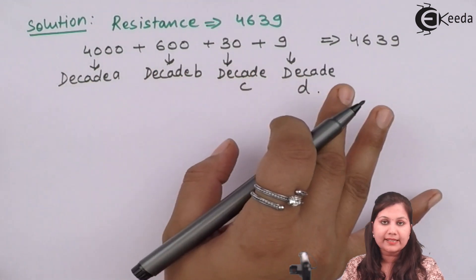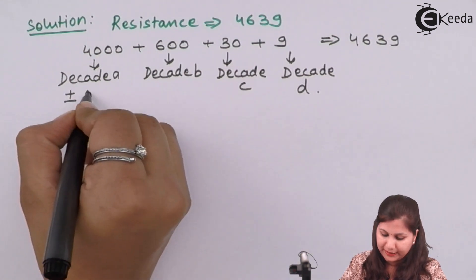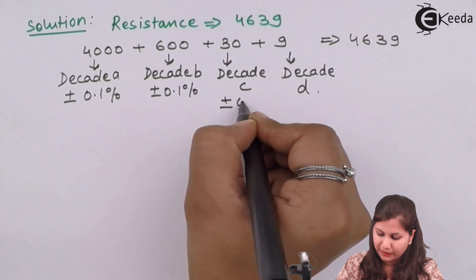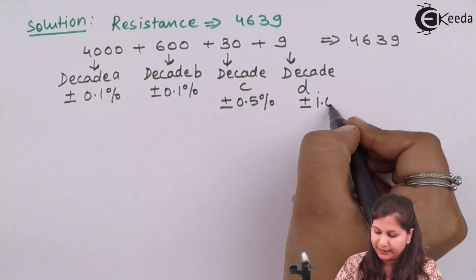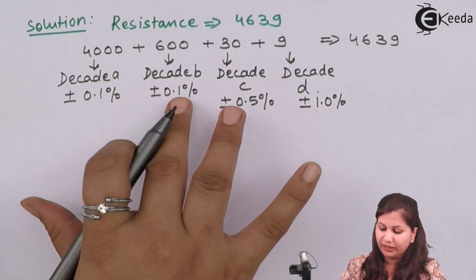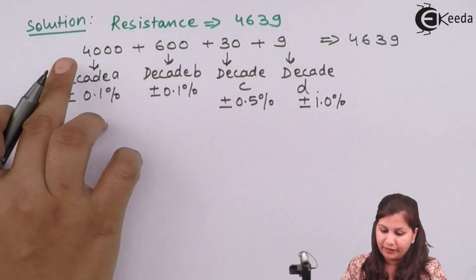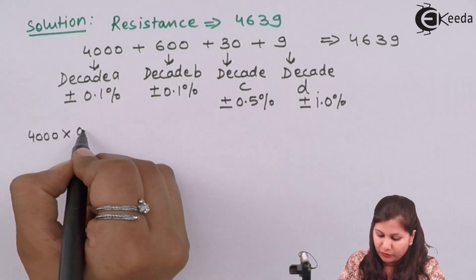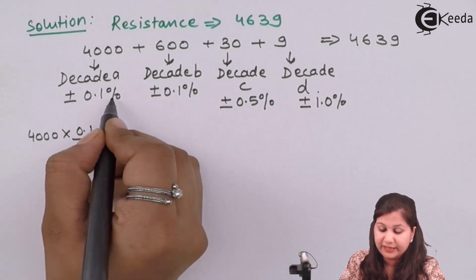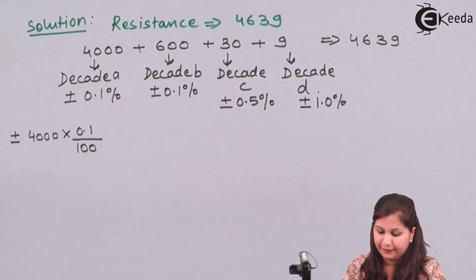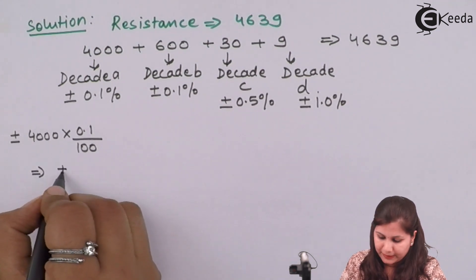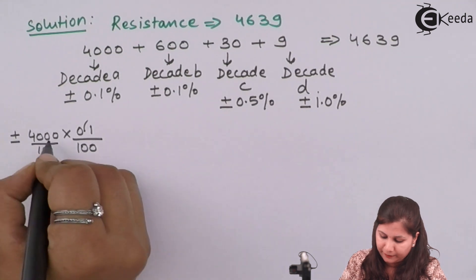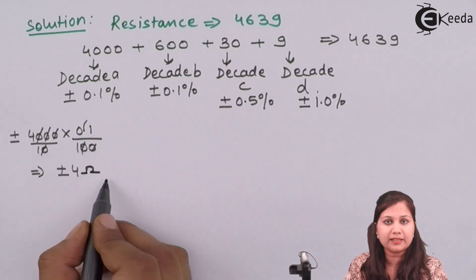The error in each decade is: decade A has ±0.1%, decade B has ±0.1%, decade C has ±0.5%, and decade D has ±1%. For decade A reading 4000: error = 4000 × 0.1/100 = ±4 ohms.